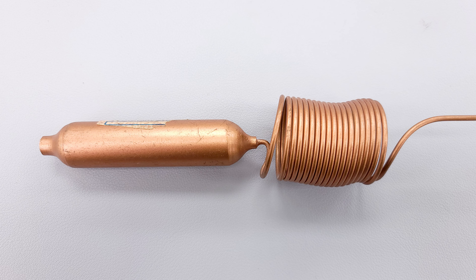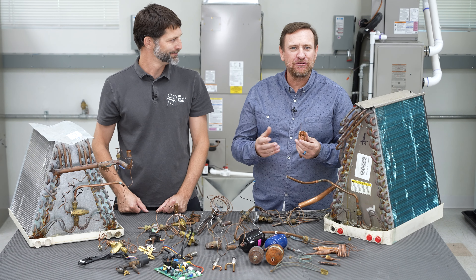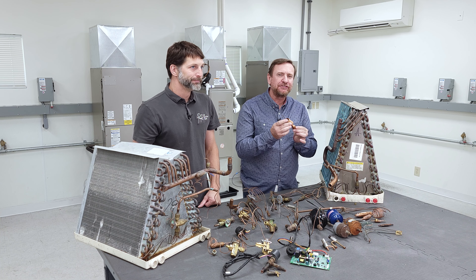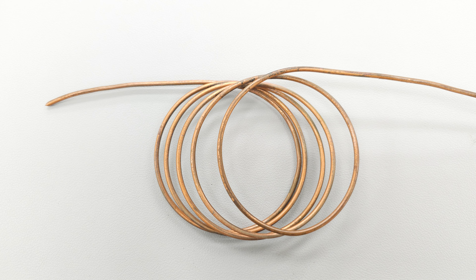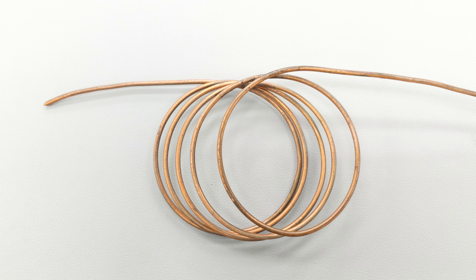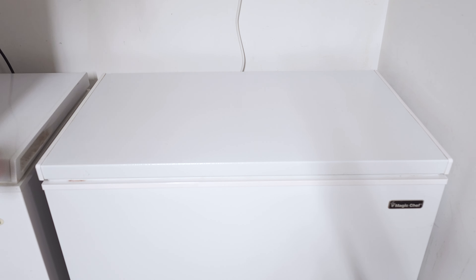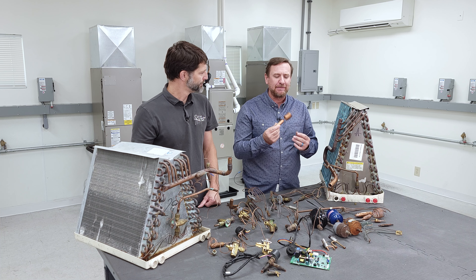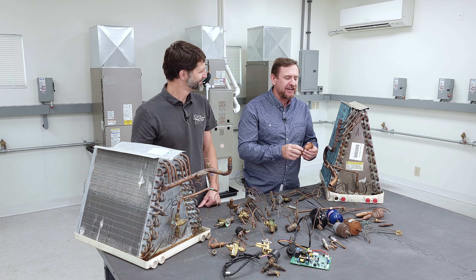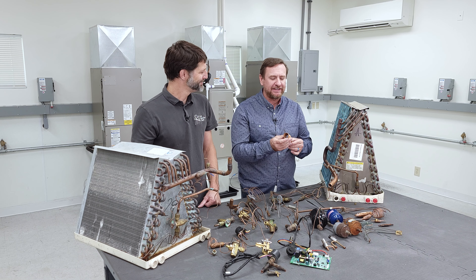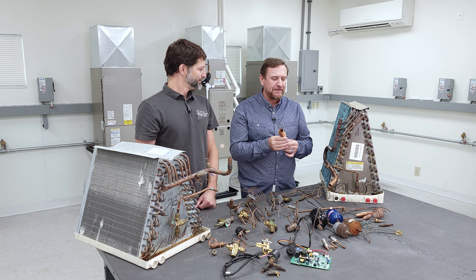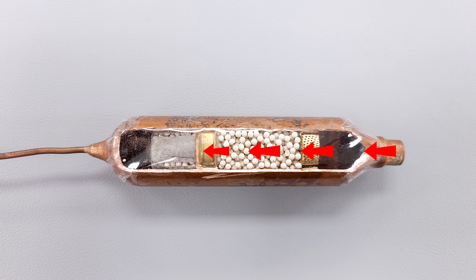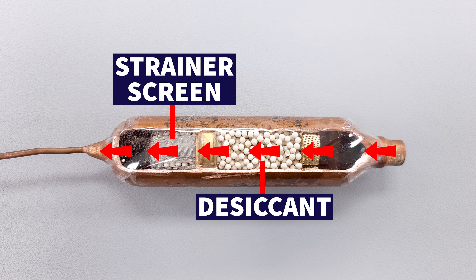The capillary tube is a great metering device from back in the day. You still see these used today in refrigerators and freezers, but the idea was not only the size of this tubing but also the length — it caused the right amount of restriction to control the flow into the evaporator. They work really well when you don't have a lot of varying load, such as a freezer inside the house where the outdoor and indoor temperatures stay consistent. For air conditioning systems, even though they were cost-effective, they didn't control the flow all that well, and the length of the tubing was an issue — they could easily get stopped up, so a strainer was used to keep the tubing clean.